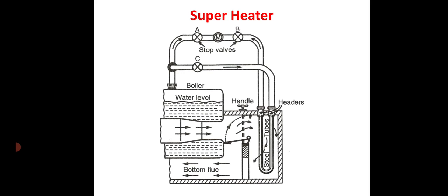The overheating of superheater tubes is prevented by the use of a balancer damper, which is operated by a handle. The superheater is in action when the damper is in position. If the damper is in vertical position, the gases pass directly into the bottom flue without passing over the superheater tubes. In this way, the superheater is out of action. By placing the damper in an intermediate position, some of the gases will pass over the superheater tubes and the remainder will pass directly to the bottom flue.